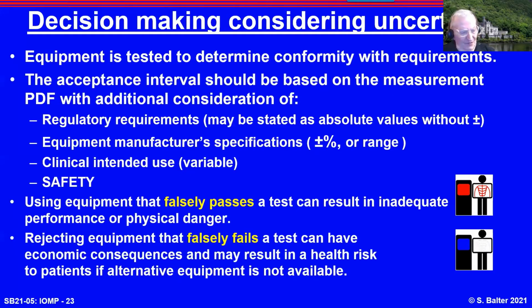The manufacturers give specifications. They usually give a plus or minus. The clinical intended use is your decision, and it has to be looked at carefully. Again, equipment that falsely passes a test can be inadequate or physically dangerous. Rejecting equipment can be economically expensive if the patient goes to the next hospital for diagnosis or treatment, and can be a real health risk if you're taking something offline unnecessarily and the patient has nowhere else to go. So these are more than check boxes. These are things in both instances that affect patients' health.